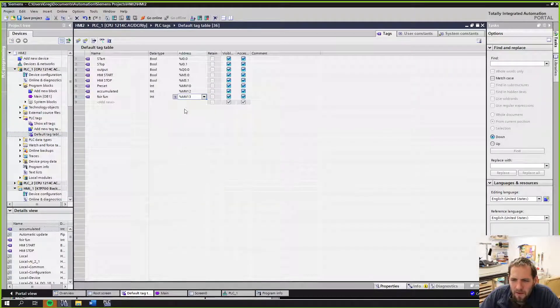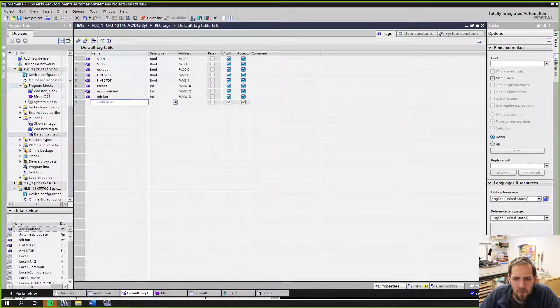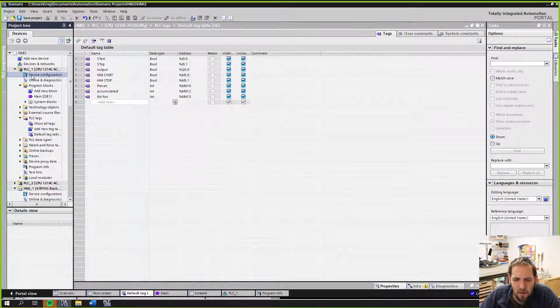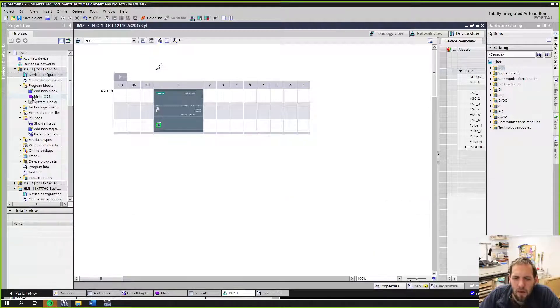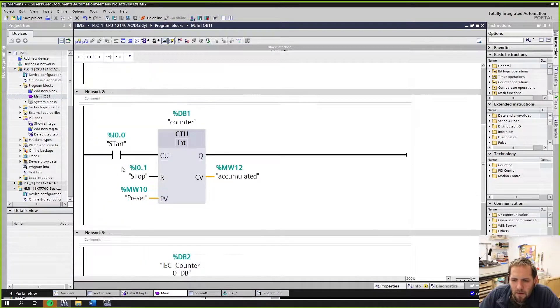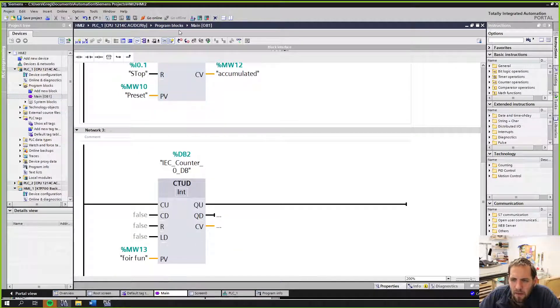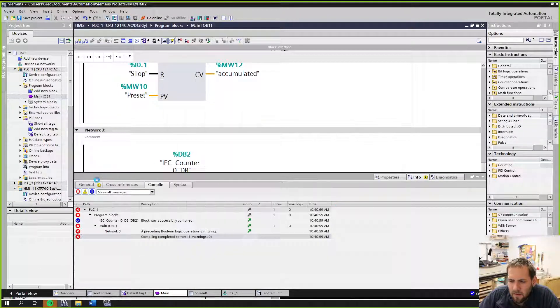Let's go back to our tags to look at those. Addresses 12 and 13 are our accumulated value. As we count, that number is going to change. 'For fun' at address 13 is our non-accumulated preset value. Let me go into device configuration, get my system and clock memory, go back to main, and instead of a manual input, we'll use a 10 Hz clock. Let's download this.